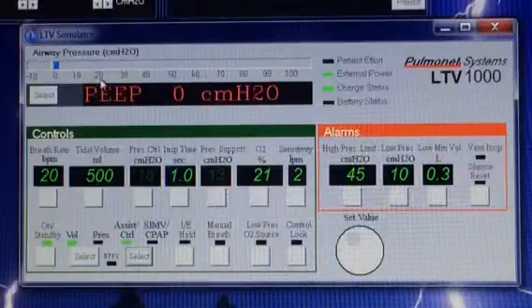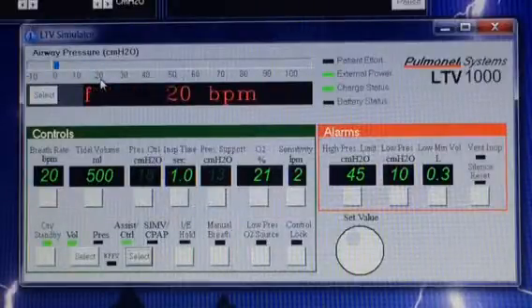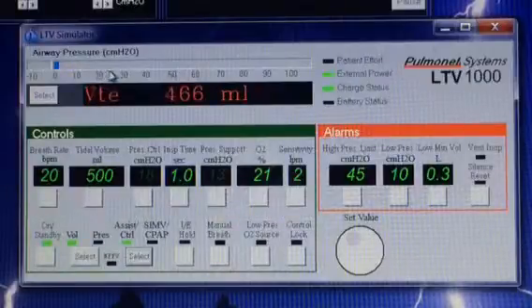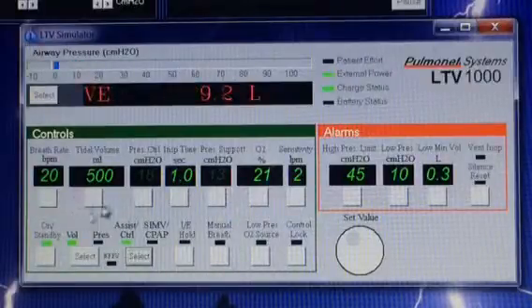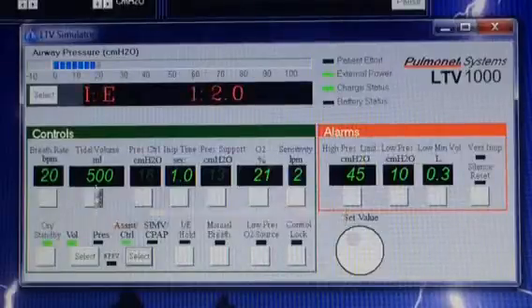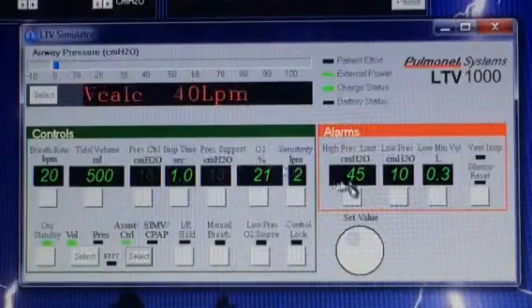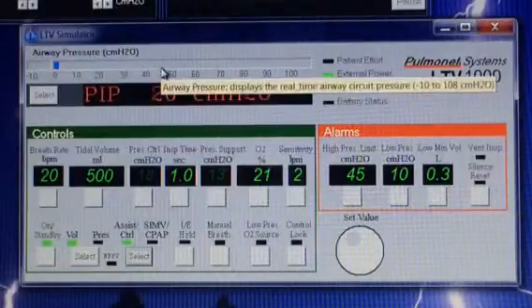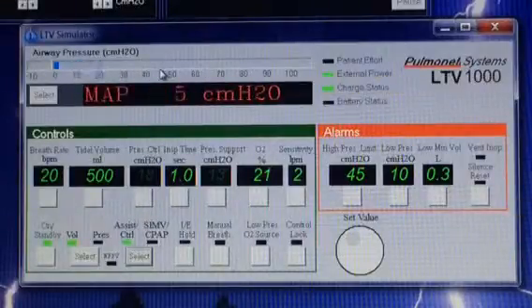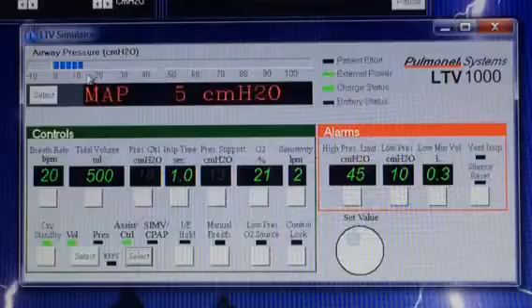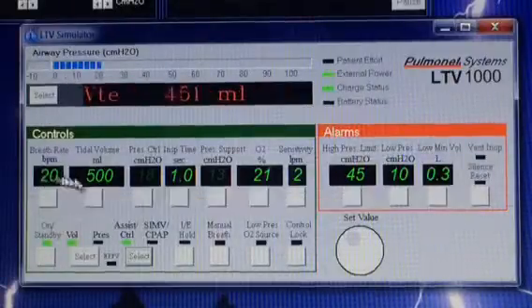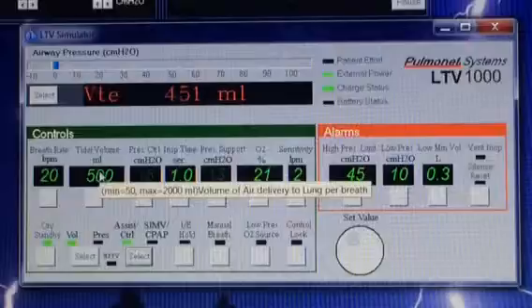Right now it's only going up to about 20 of pressure. But if you get congested or you cough, it'll push harder and harder until it gives you that 500 milliliters of volume. The only thing that will stop it is the high pressure limit. Once it goes up to 45, it will stop that breath immediately, let them exhale, and it will alarm high pressure. Then it will try again with the very next breath to give that 500 milliliters of volume.